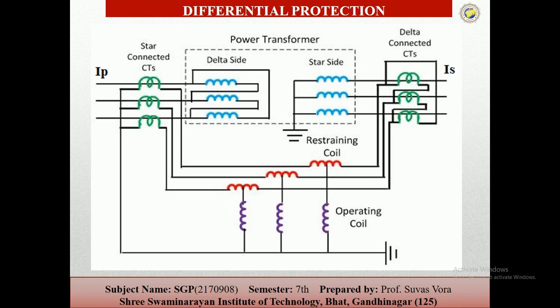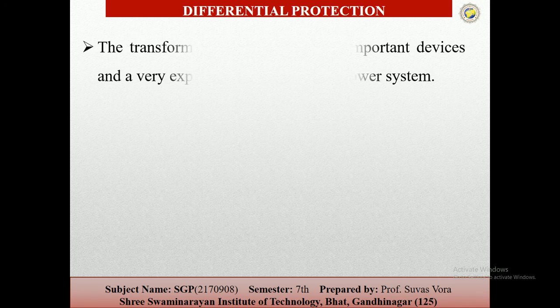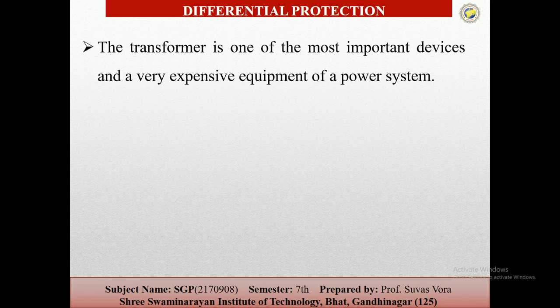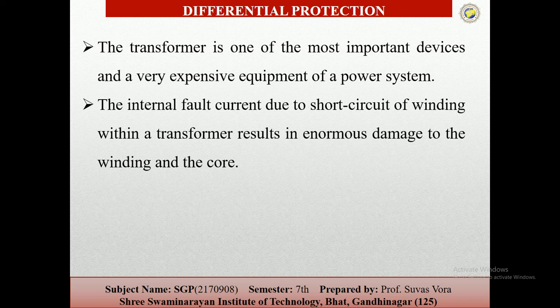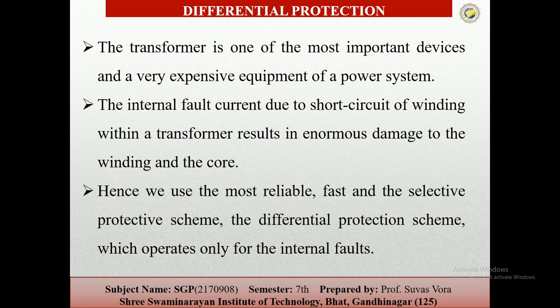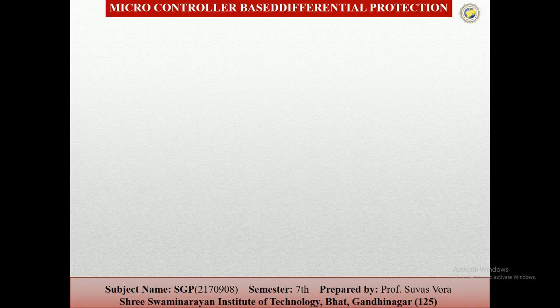Now we can learn about the microprocessor. So the transformer is one of the most important devices. We know that it is very expensive equipment, and the internal fault current due to the short circuit of winding within the transformer results in enormous damage of the winding and core. Enormous means के जो undesirable damage है वो होता है. So hence we use the most reliable, fast and selective protective scheme, the differential protection scheme, which operates only for internal faults. Now we can study about the microcontroller.